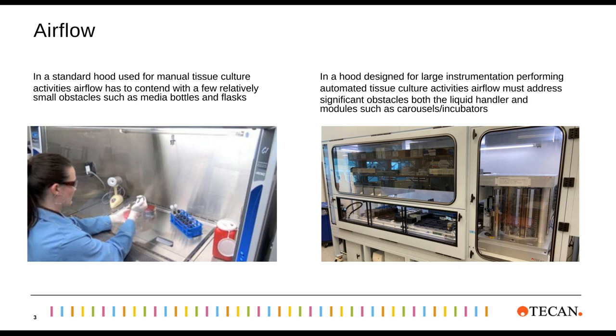The other major consideration, and David will talk a lot more about this in his presentation, is to think about airflow. You can't just put a liquid handling instrument into a standard hood and hope that it'll work well. Regular laminar flow hoods are designed for a small number of obstacles in there, such as media bottles and flasks. When you put in a large instrument, you have to consider the instrument itself and how the airflow will work. And that's very much part of the design of the types of hoods that we offer and put together.